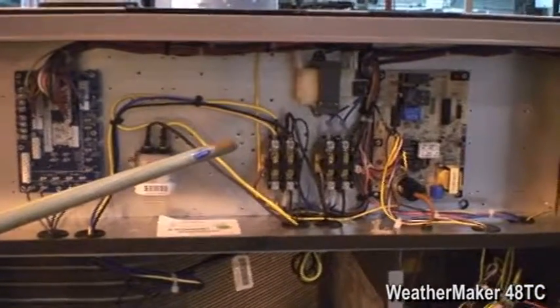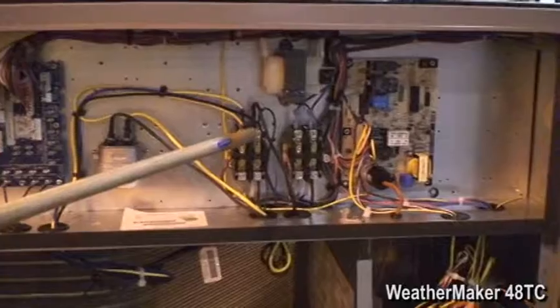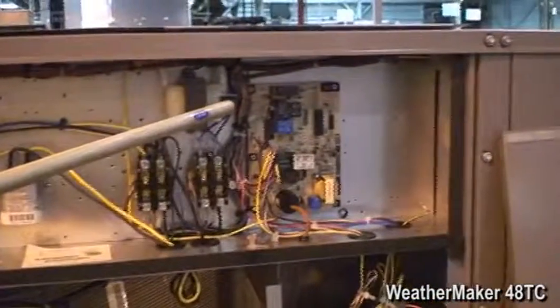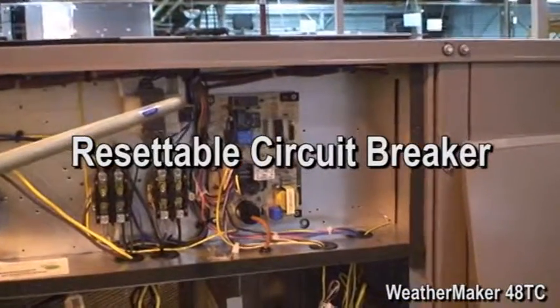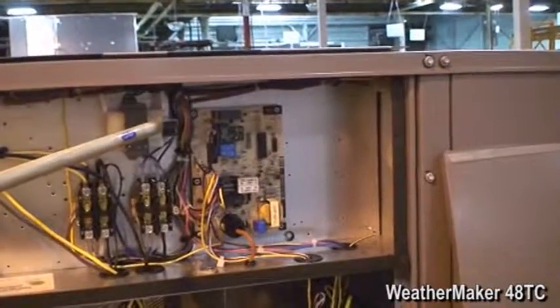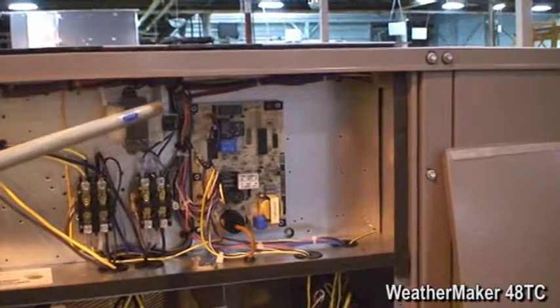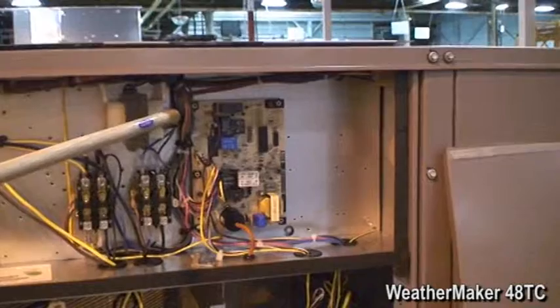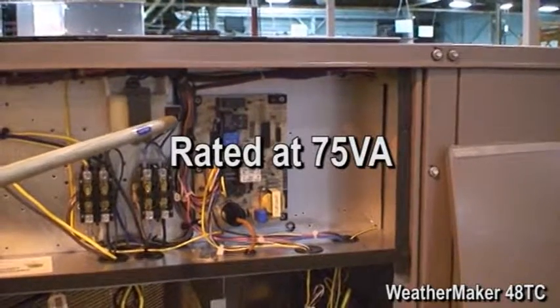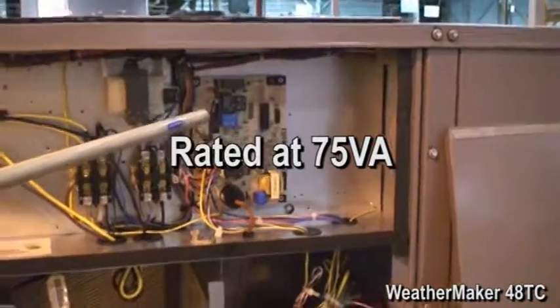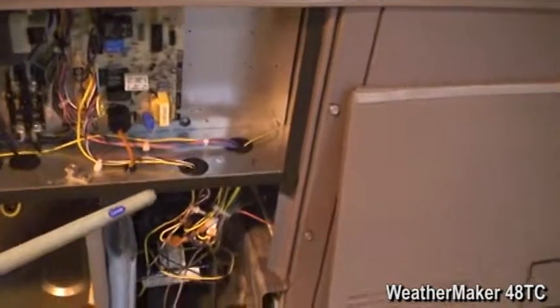But note that unlike the competitor's unit, the transformer in the Carrier unit has an integrated resettable circuit breaker. This means direct wiring to the 24-volt side of the transformer is well protected. It is also rated at 75 VA, higher than the competitive model, something else appreciated by the review team.